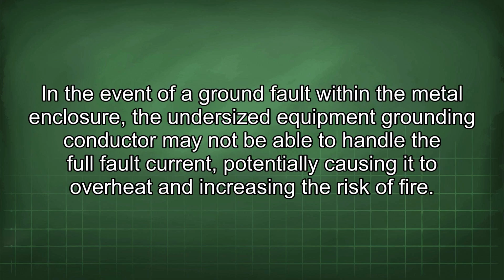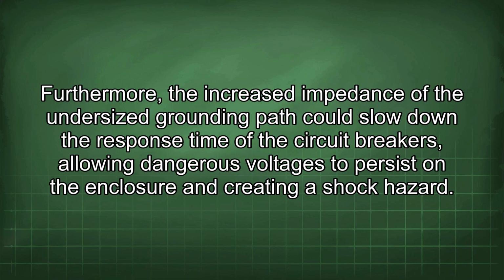In the event of a ground fault within the metal enclosure, the undersized equipment grounding conductor may not be able to handle the full fault current, potentially causing it to overheat and increasing the risk of fire. Furthermore, the increased impedance of the undersized grounding path could slow down the response time of the circuit breakers, allowing dangerous voltages to persist on the enclosure and creating a shock hazard.